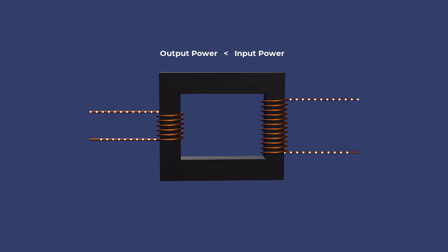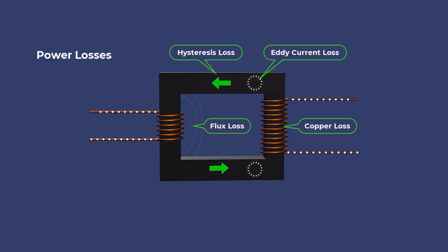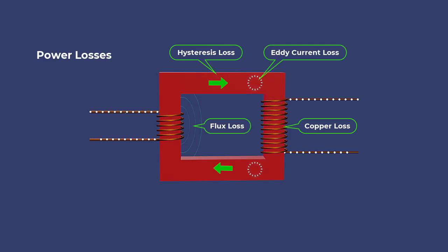The output power is always slightly less than the input power. Real transformers have power losses, including copper loss, hysteresis loss, flux loss, and eddy current loss, which end up as heat that must be removed from the transformer.